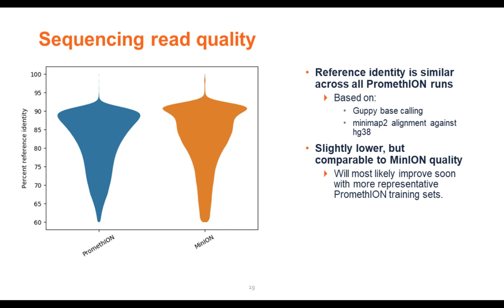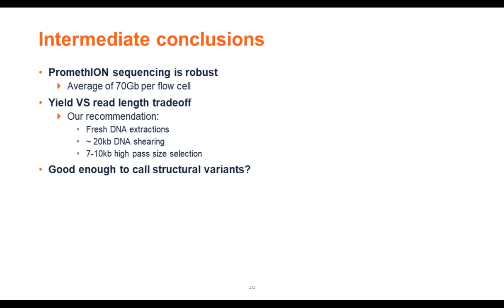For quality, we show the percentage reference identity — the similarity of sequencing reads against the reference genome after base calling and alignment. We get rather comparable qualities to MinION, though slightly lower, likely because base calling for PromethION is not yet as optimized as for MinION, and we expect these qualities will be equivalent in the near future. Our intermediate conclusion: PromethION is very robust, averaging 70 gigabases per flow cell. Best practices are to use fresh DNA, shear to approximately 20 KB, and use size selection for fragments above 7–10 KB.